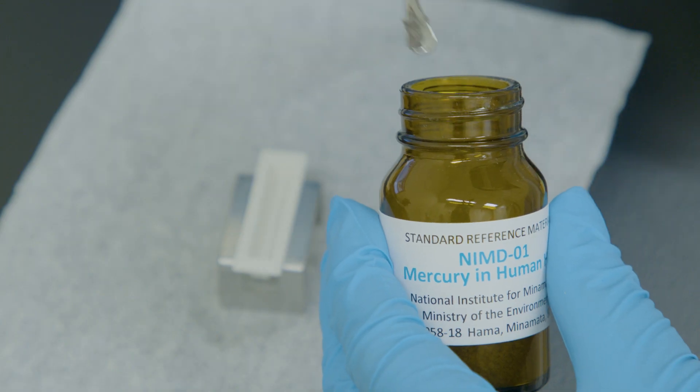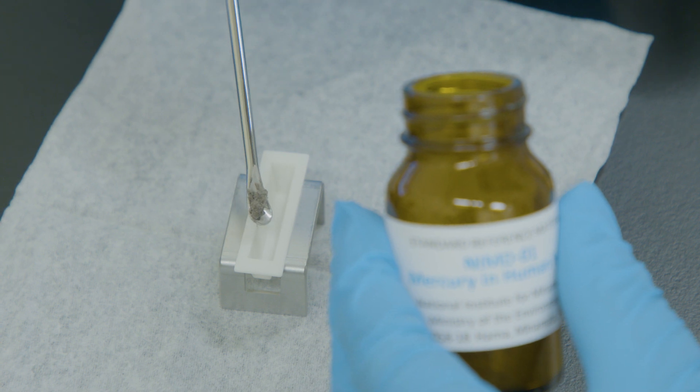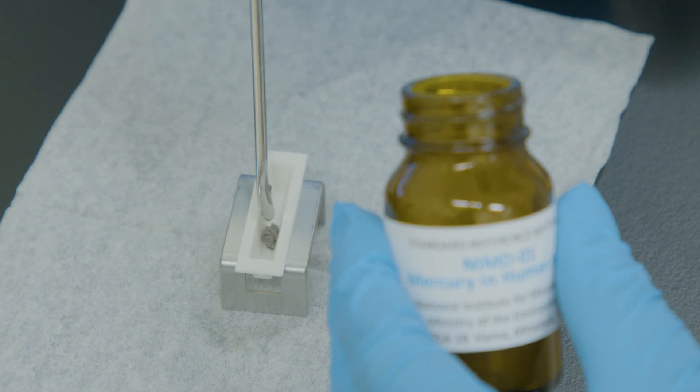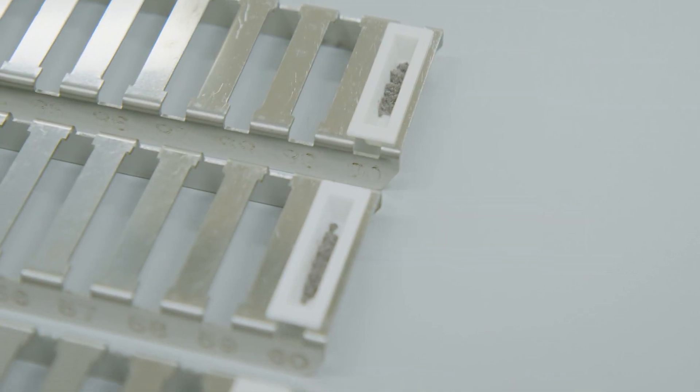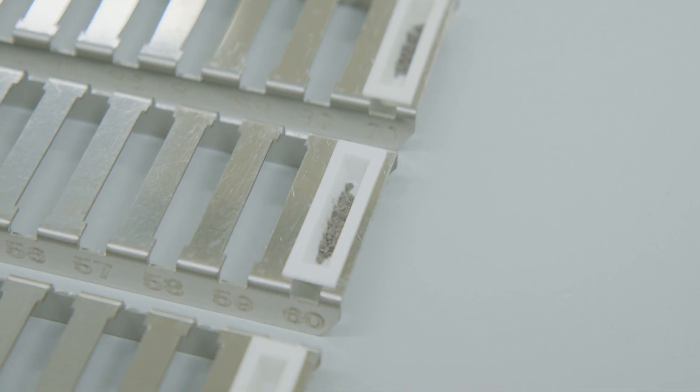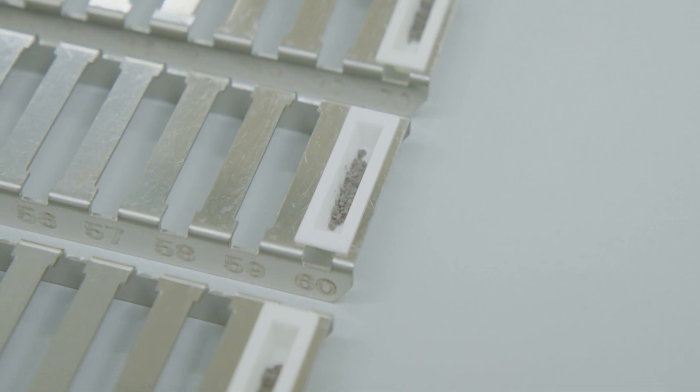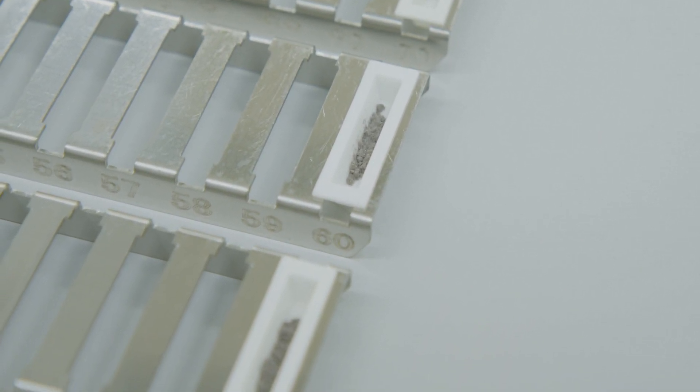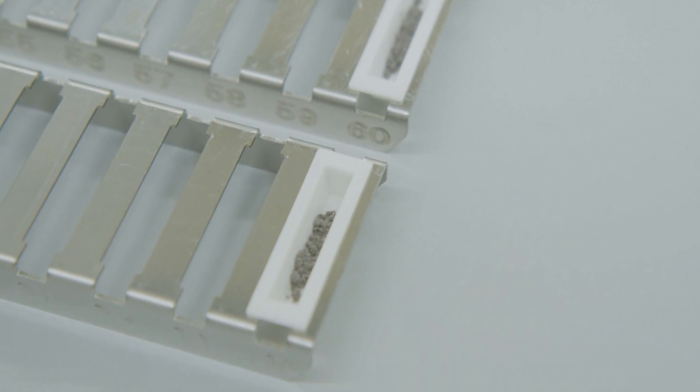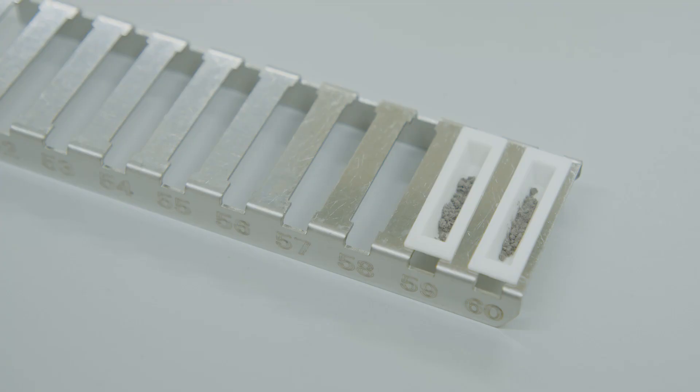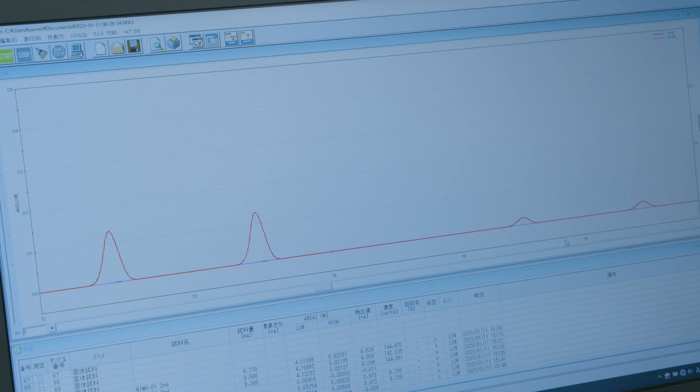It is also essential to perform a duplicate analysis to ensure the precision of our results. Inclusion of the same sample every 10 samples is generally recommended. If the sample size is too small for multiple analyses, we can use reference materials instead. Regularly measuring reference material or standard solutions will help confirm that the instrument's sensitivity is stable. To ensure the results are consistent daily, it is recommended to analyze the same sample, ideally a CRM.